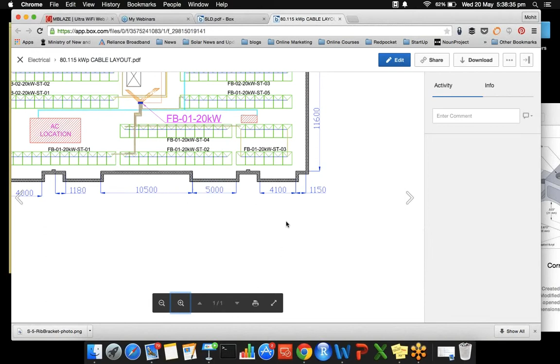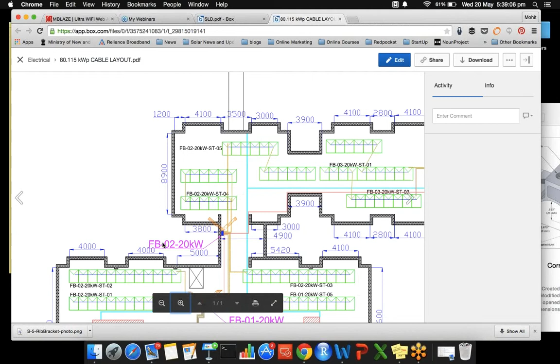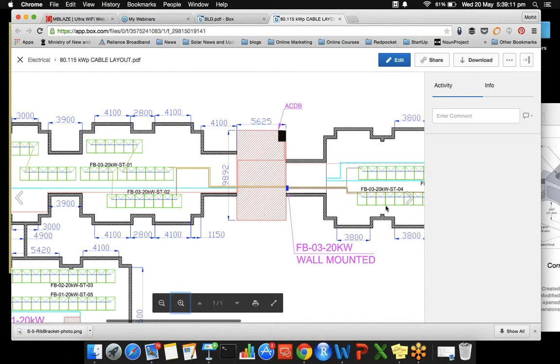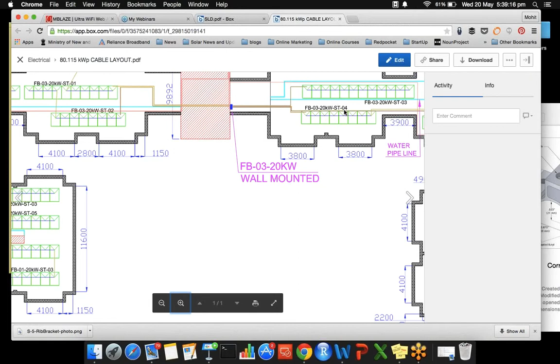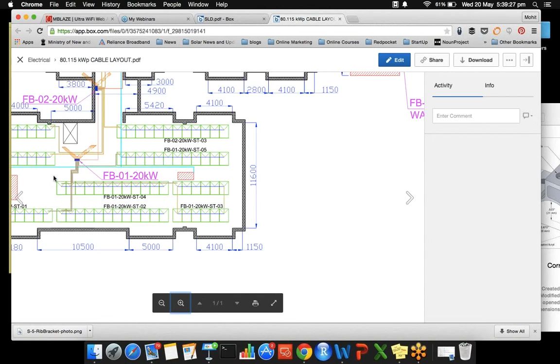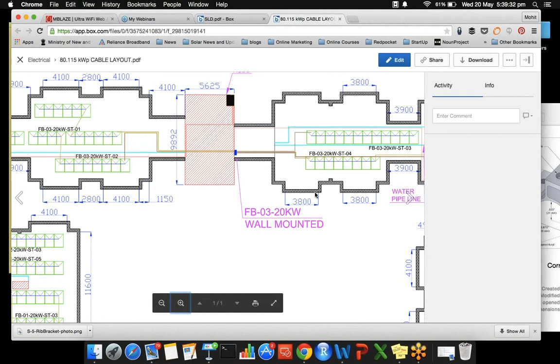The modules are labeled as FB0120KWST01. This is one table of modules, and the cables from this table are connected to inverter one, which is right here in this blue box labeled FB0120KW. The cables from the second table, that is 02, are connected to the inverter FB0220KW. Similarly, for inverters 03 and 04, the cable connections from the respective module tables have been provided. As you can see, the cable route is clearly visible and easy to understand from the modules to the inverters. This is the detailed drawing of the cable layout.